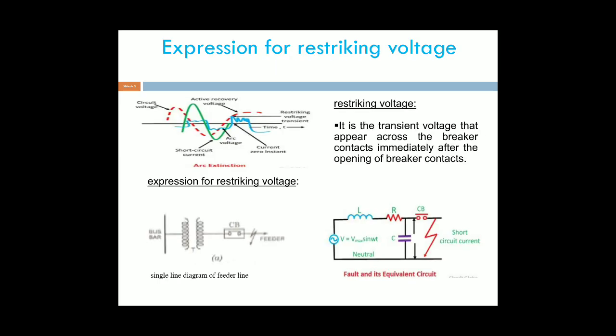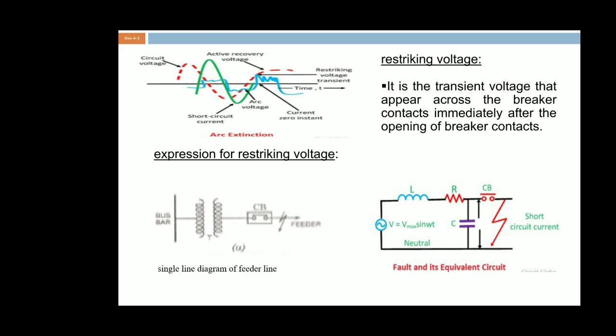The expression for restriking voltage is, first, what is meant by the restriking voltage? It is the transient voltage that appears across the breaker contacts after opening of the breaker. For every current zero interruption, the arc is interrupted but it does not normalize instantly, it will oscillate. There will be a transient condition at this interruption of the arc. The voltage across the contacts is known as the restriking voltage.